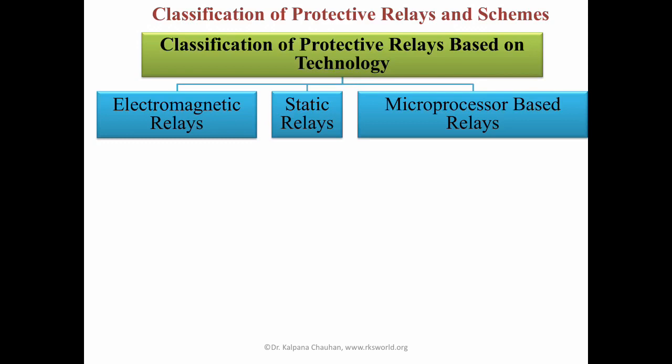electronic components. There is a comparator circuit in the relay which compares two or more currents or voltages and gives an output which is applied to either a slave relay or a thyristor circuit. The slave relay is an electromagnetic relay which finally closes the contacts. A static relay containing a slave relay is a semi-static relay.